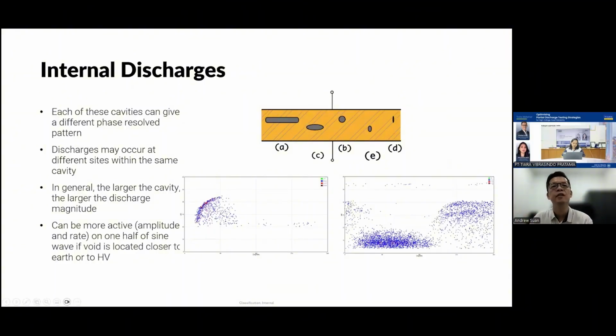So internal discharge, how does it look like? At EA Technology, we've been working with PD for 60 years - in fact this year we celebrate 60 years in the business. With all this experience, and from our database and day-to-day course of work, we can more or less identify what type of PD it is by looking at the PRPD plots. Each cavity can give a different phase resolved pattern, so different types of problems will demonstrate different waveform patterns in the PRPD plot. The main thing we really want to see is two clusters 180 degrees apart - this is the main thing that helps us identify whether it's a real PD or noise.